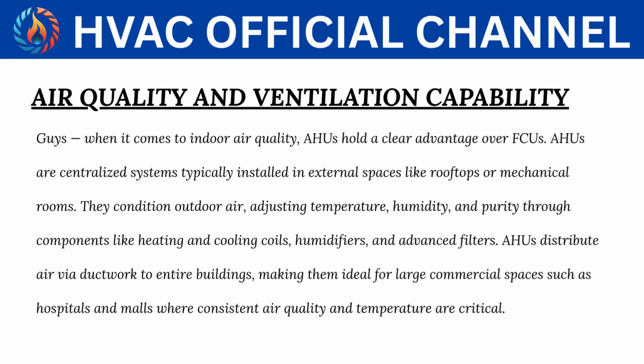Air quality and ventilation capability. Guys, when it comes to indoor air quality, AHUs hold a clear advantage over FCUs. AHUs are centralized systems typically installed in external spaces like rooftops or mechanical rooms. They condition outdoor air, adjusting temperature, humidity, and purity through components like heating and cooling coils, humidifiers, and advanced filters. AHUs distribute air via ductwork to entire buildings, making them ideal for large commercial spaces such as hospitals and malls, where consistent air quality and temperature are critical.